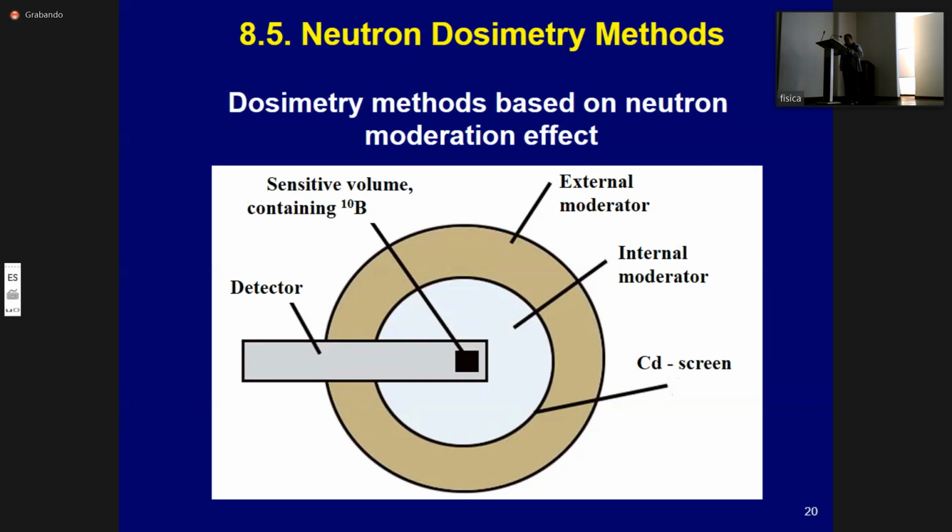In some cases, nevertheless, it may be necessary to measure the neutron spectrum, for example, when it is necessary to clarify the parameters of biological protection. For this, neutron dosimeters with a set of moderators in the form of spheres of various diameters are used. They are the so-called Bonner spheres. Such a spectrometer is called a multi-sphere spectrometer. Measurement of the neutron spectrum makes it possible to more accurately estimate the ambient dose equivalent rate.